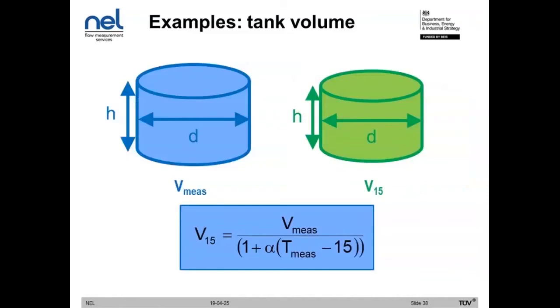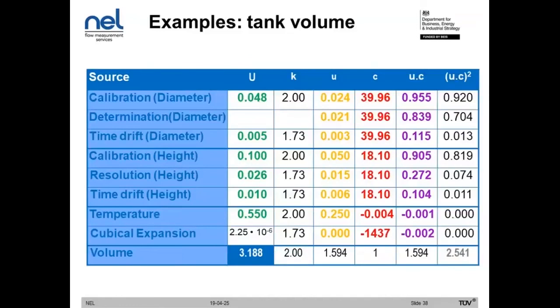But actually, there's some other things to consider. So local conditions like temperature will have an effect, and we have to consider the expansibility of the material. So there is a correction to be applied. If we take a standard temperature of 15 degrees Celsius, we might find that we measure under different conditions. So maybe we've measured the tanks at 30 degrees Celsius or 0. So we have to convert. But once that is done, we have a corrected volume measurement. So the calculation becomes slightly more complicated.